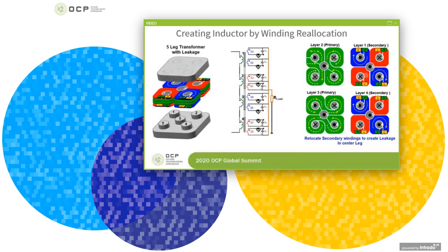Here is a 3D picture of how the 5-leg transformer looks. For this modification, we only used one extra 5th leg at the center between all the transformers, utilizing the unused area between the 4 transformers. We use exactly the same primary winding, so we don't change anything from the primary winding point of view, and we only swap secondary windings without adding any extra winding or termination.